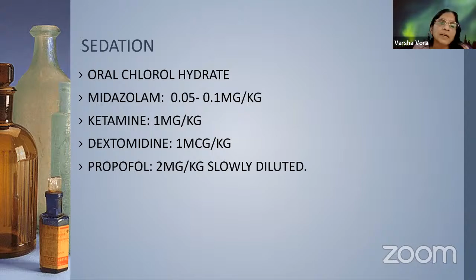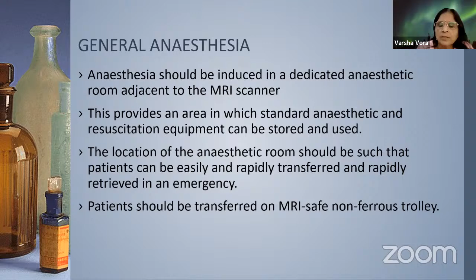General anesthesia should be induced in a dedicated anesthetic room adjacent to the MRI scanner. This provides an area in which standard anesthetic and resuscitation equipment can be stored and used. The location of the anesthetic room should be such that the patient can be easily and rapidly transferred, and rapidly retrieved in an emergency. The patient should be transferred on an MR-safe non-ferrous stretcher. A mask with non-ferromagnetic components must be chosen.